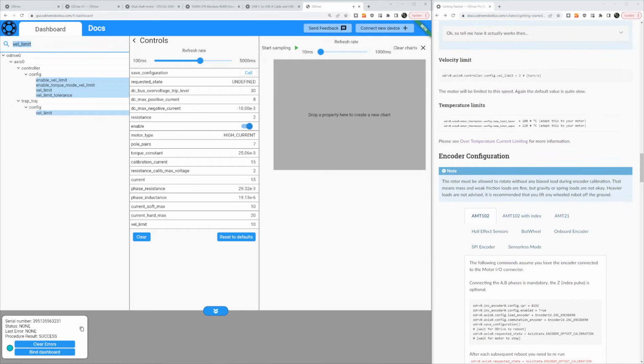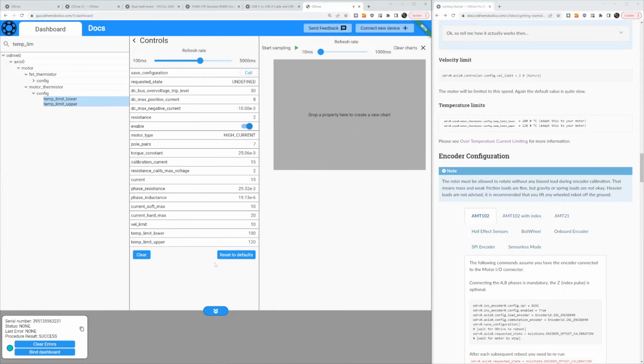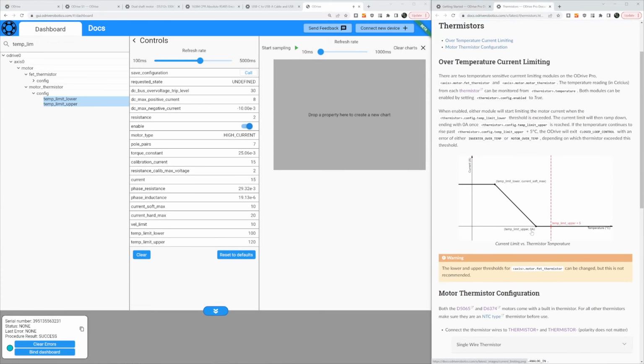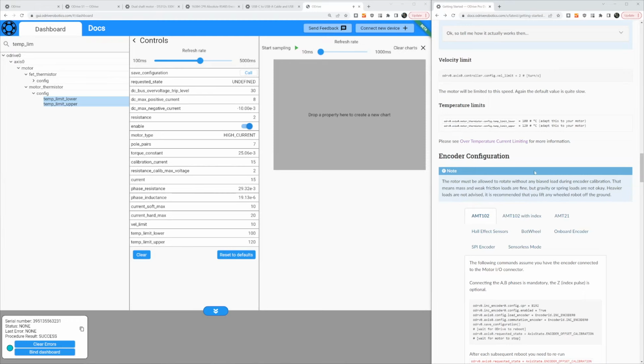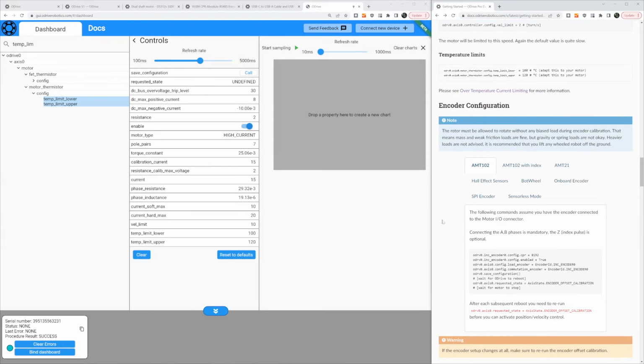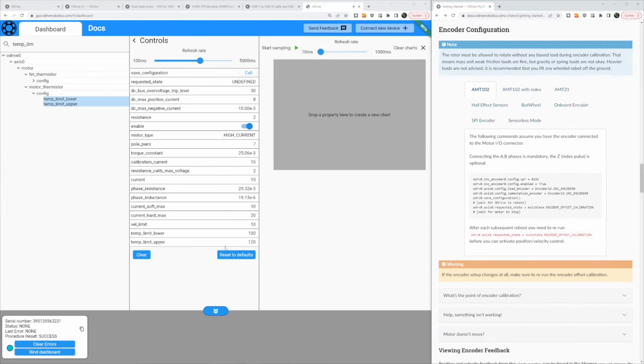Temperature limits. All right. I would not suggest changing the FET thermistor. That's for the inverter. Those defaults are good. But the motor thermistor, we can have a look. It basically has a ramp where it ramps down the current when you're within the range of these configured points. It will start scaling back the current at 100 degrees Celsius and reach a 0 point at 120. This is usually reasonable for many motors. We don't have the motor thermistor set up in this session, so it won't be used, but if you have the motor thermistors working, this will be useful.